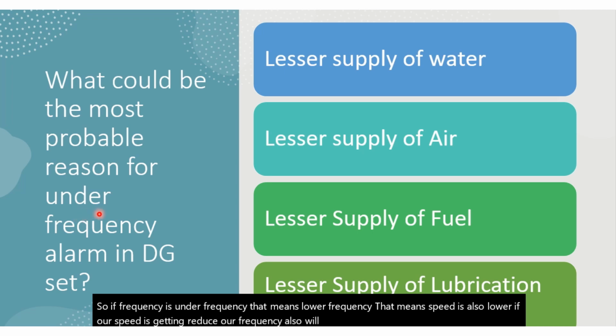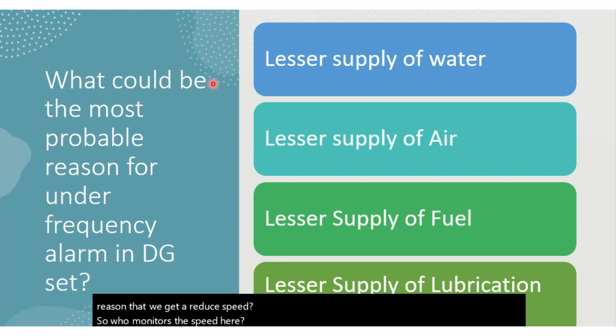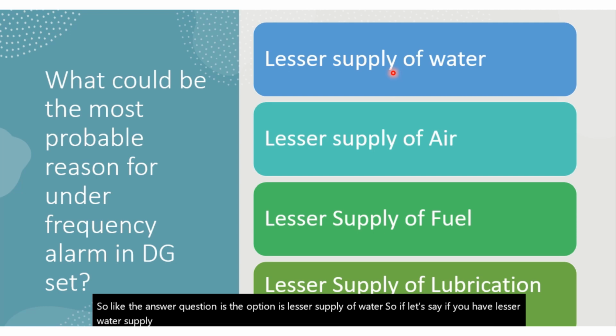If our speed is reduced, our frequency will also be reduced. So what is the main reason that we get a reduced speed? The first option is lesser supply of water. If we have a lesser water supply, if the coolant water has leaked, what will happen? It will create high temperature and further tripping. It will not create under frequency.